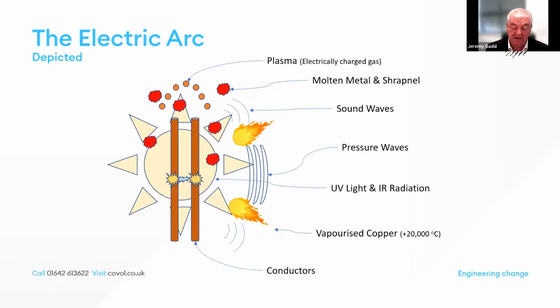This simple depiction shows a number of events that happen very quickly during an arc flash. You have electrically charged gas, which is plasma, emitted and further supporting the production and duration of an arc. Ultraviolet light and infrared radiation are emitted from the arc center, and the resultant explosion and heat result in the vaporization of copper bus bars or other molten metal, with shrapnel being emitted along with a pressure blast wave and sound waves. It is very, very destructive.